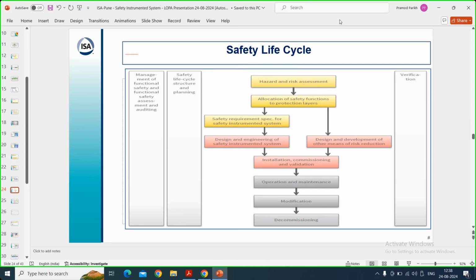Whereas LOPA is a semi-quantitative analysis. Your consequence is subjective: risk is high, severe, very high, intolerable. These are all qualitative assignments to the consequence. But the probability of failure of the devices in the system is based on quantitative failure data, maybe the maintenance data or the manufacturer's data. Best is the maintenance data. If the plant has data showing that there are 200 solenoid valves and 2 valves failed in 5 years, this is quantitative data of probability of failure. So LOPA uses quantitative failure data to derive the probability of failure.